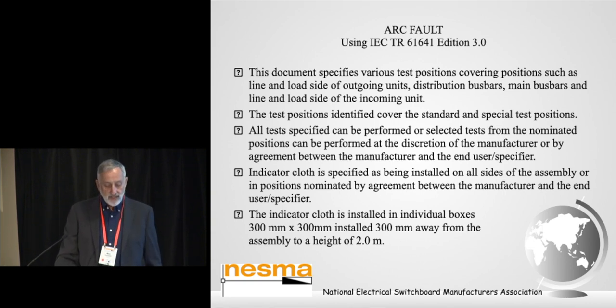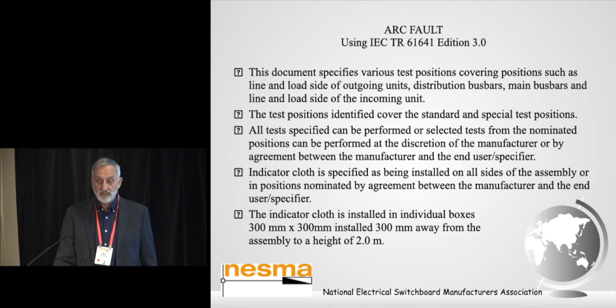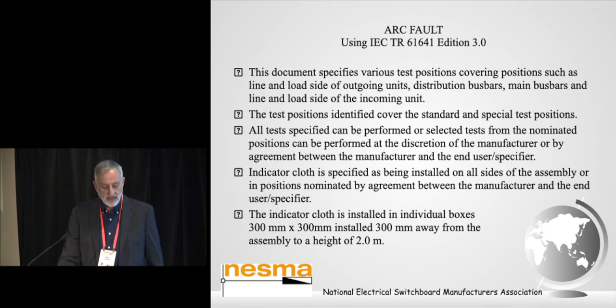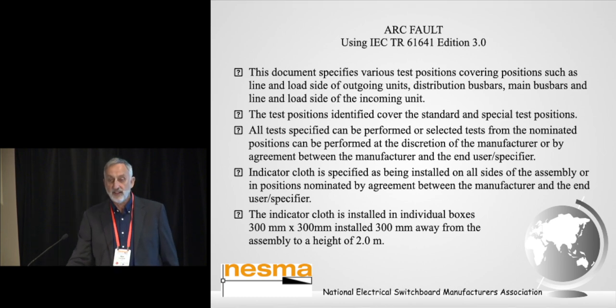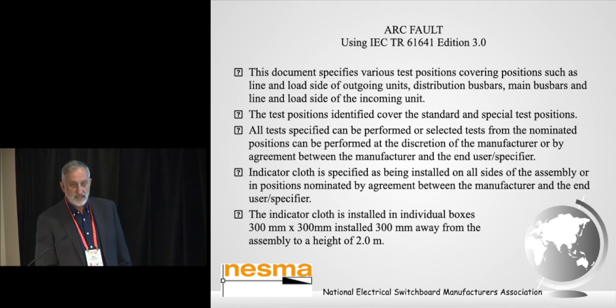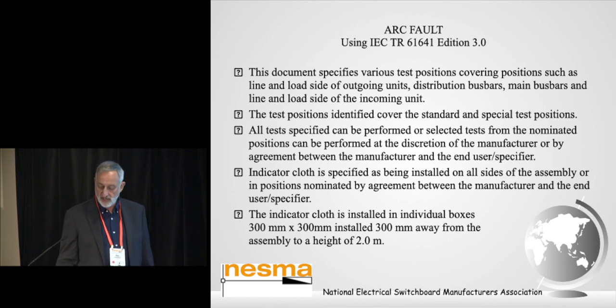Indicator cloth is installed on all sides, not only the front of the assembly, or in positions nominated by agreement between the manufacturer and specifier. And the indicator cloth is in 300 by 300 squares, 300 mm away from the assembly, and at a height of only 2 metres. But the indicators are then installed in a checkerboard fashion.